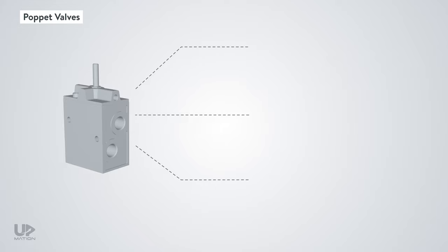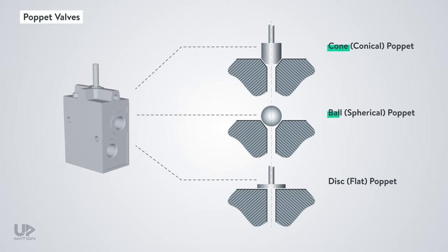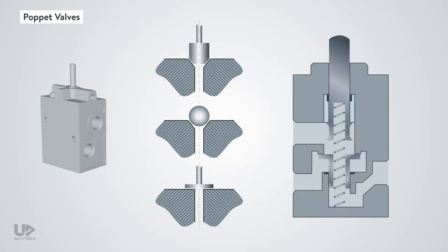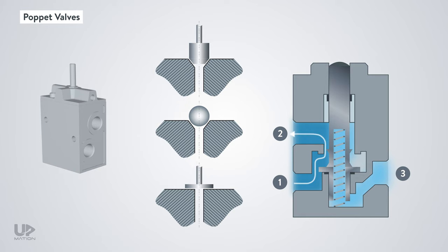Poppet valves have different types depending on the type of closing element that has been used in them. For instance, this is a simplified cross-section of a disc poppet valve. When the valve is unactuated, the flow is from 2 toward 3. And when the valve gets actuated, the valve sits on the disc and the path from 1 toward 2 gets open.